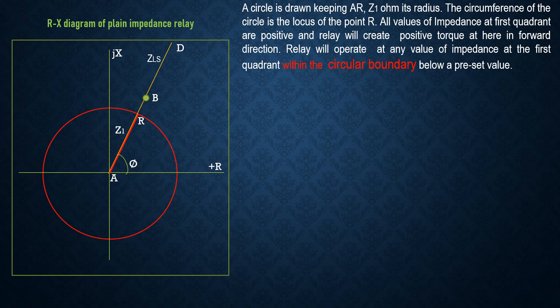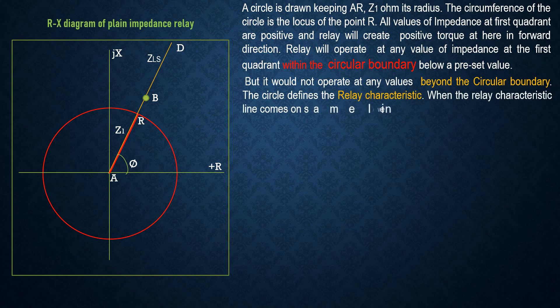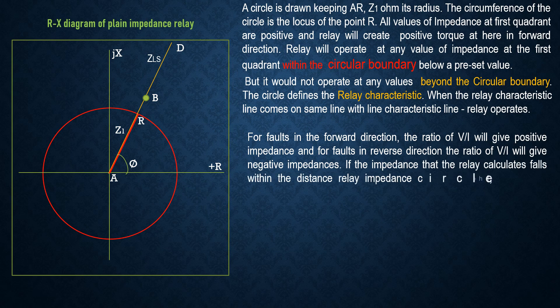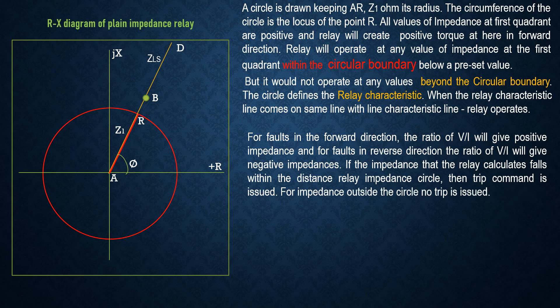The relay operates at any impedance value within the circular boundary below a preset value, but does not operate beyond the circular boundary. The circular boundary defines the relay characteristics. When the relay characteristics line coincides with the line characteristics line, the relay operates. For faults in the forward direction, V/I gives positive impedance; for faults in the reverse direction, V/I gives negative impedance. If the impedance falls within the distance relay impedance circle, a trip command is issued; for impedance outside the circle, no trip is issued.